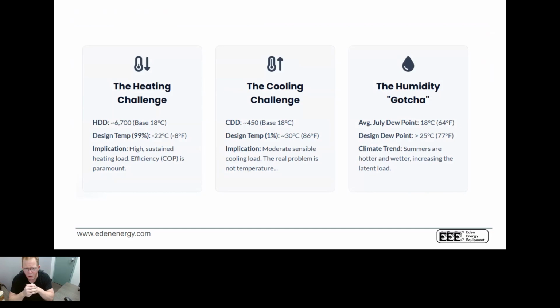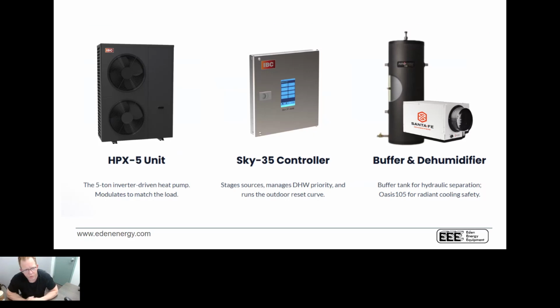And with the way that loads are shrinking and shrinking, we cannot rely on cooling to take care of that latent cooling load because the equipment's not running as long. So you end up with thermal comfort issues that will show up whether it's an air to water or an inverter-driven air to air system. We just have to understand what we're dealing with and what it looks like. In this particular case, I'm using what's in my own home as a great example to illustrate what I'm doing. There are a few variables that are not in my home that we're going to talk through, but the key is that everything we're talking about right now you can do.